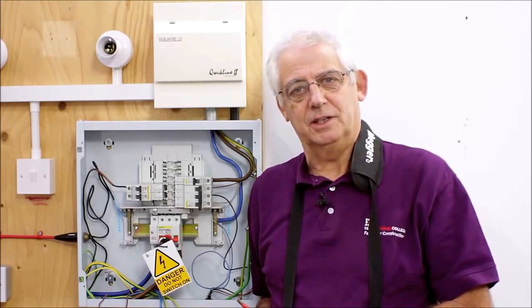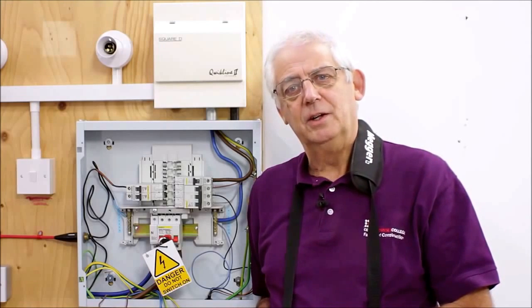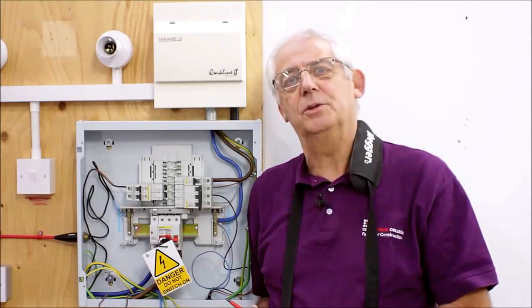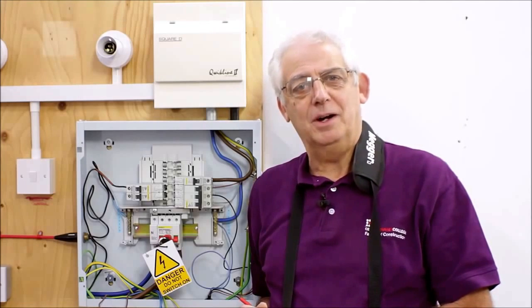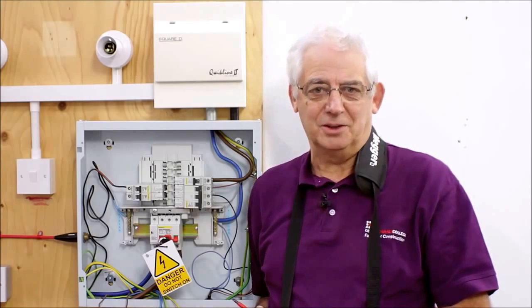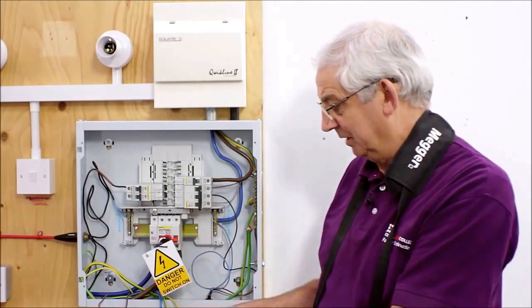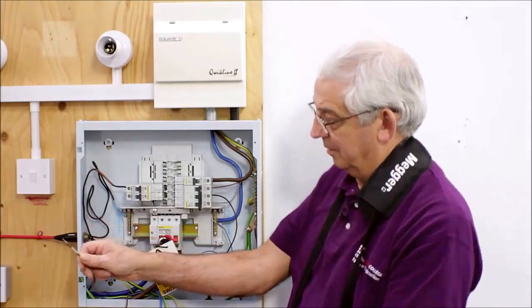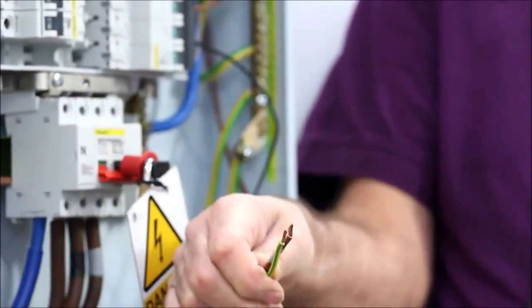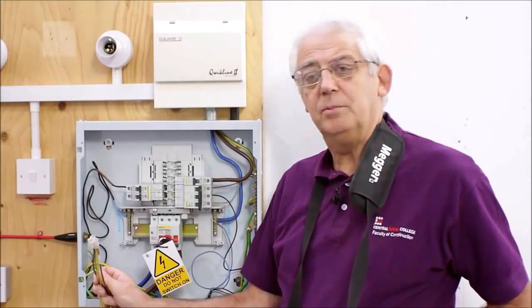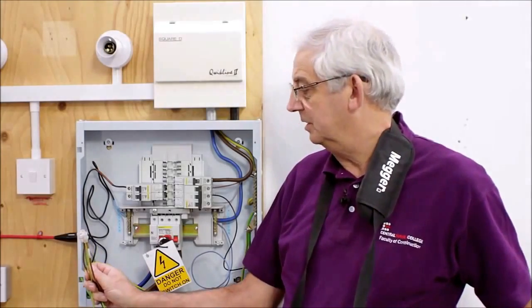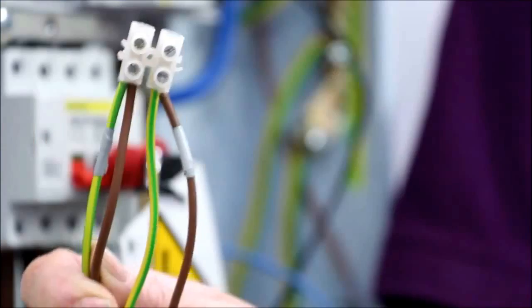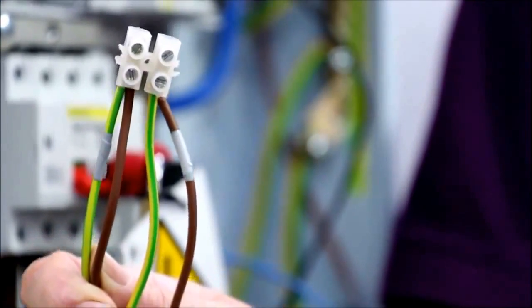What I need to do now that I've got the measurement of 0.23 for each conductor is join together one marked line conductor to an unmarked earth conductor and a marked earth conductor to the unmarked line conductor. Might sound complicated, but basically I'm going to join the marked one to the unmarked one on both occasions. As you can see, I've now joined one marked one to an unmarked one on each case, so you've got a cross connection, which is really a figure of 8. Make sure the connections are tight, so it's usually better to use a block connector if you possibly can.